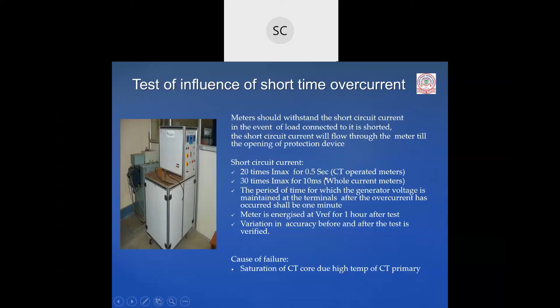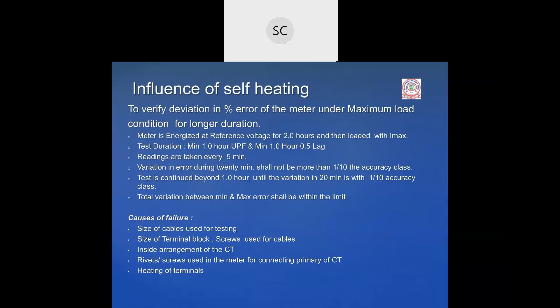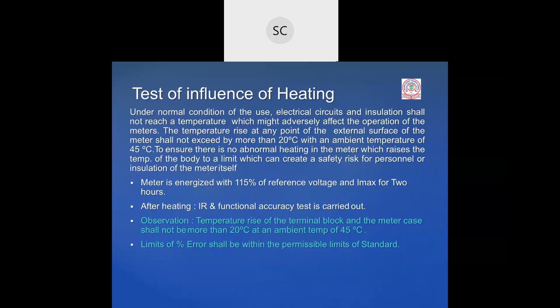Influence of self-heating. If I am drawing at my IMAX, it should continue, and my meter should not get damaged or catch fire, or show abnormal behavior. That also we have to verify. Test of influence of heating: by heating the meter at 115%, the observation is that the temperature rise of the terminal block and meter case shall not be more than 20 degrees at an ambient temperature of 45 degrees. When the meter is kept in the oven at 45 degrees, the temperature rise shall not be more than 20 degrees. It should not cross 65 in any case.